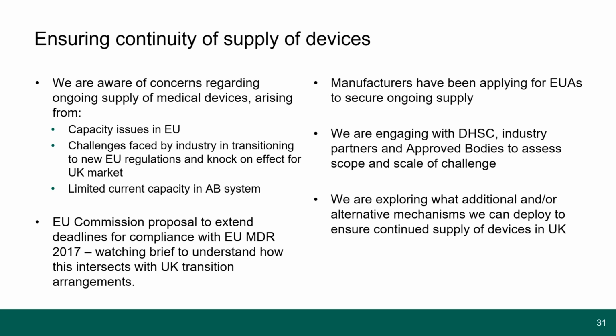And as Gillian also mentioned, we've been keeping a watching brief on developments in the EU as proposals for extending their transition timelines have taken shape. For manufacturers with CE mark devices, we'll be assessing how this fits with our own proposed extended transition arrangements. In the shorter term, some manufacturers have been applying to us for exceptional use authorisations. This process enables devices that don't have a valid CE or UKCA mark that are critical to supply to be placed on the market for a limited time whilst they're able to come back into compliance and receive their certification.